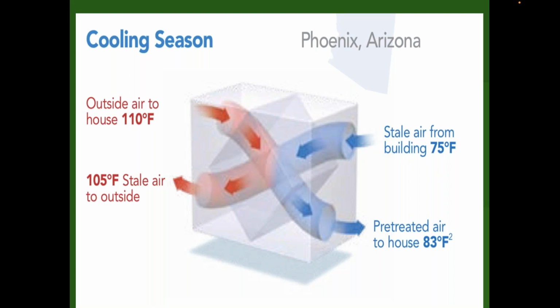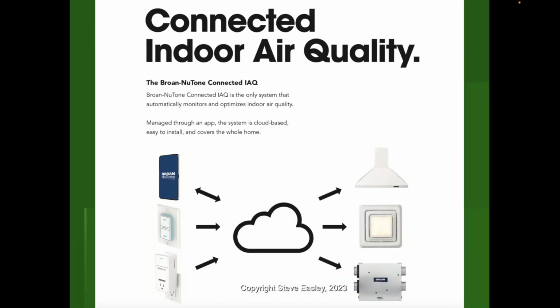And these are getting more cost effective every day, and it allows you to have fresh air ventilation without the penalty of having to reheat and recool all that air you bring into your home. Now, I also mentioned the ability to monitor your true indoor air quality and then run your ventilation system based on what that air quality is, rather than just an ASHRAE CFM per minute standard.